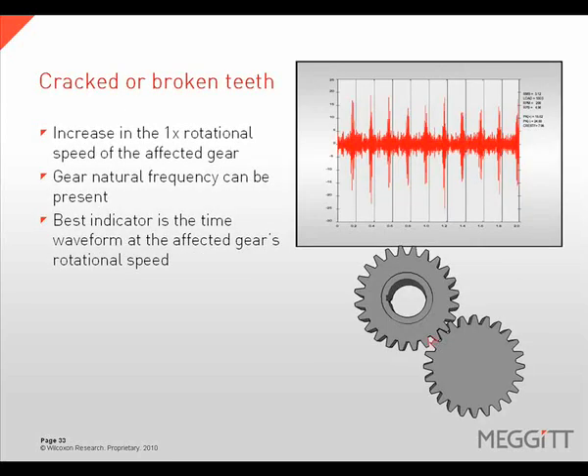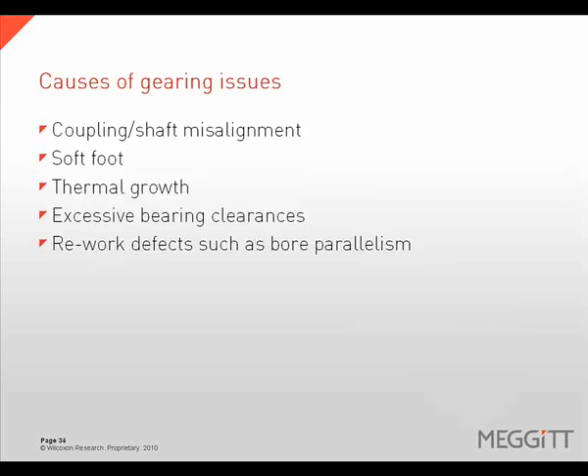Cracked or broken gear teeth will increase the amplitude of the 1x rotational speed vibration peak. The gear's natural frequency can also be present; however, the best indicator of cracked or broken gear teeth is found in the waveform, where impacting spaced at the rotational speed of the damaged gear will be evident. Many factors can cause gear related problems, such as coupling or shaft misalignment.